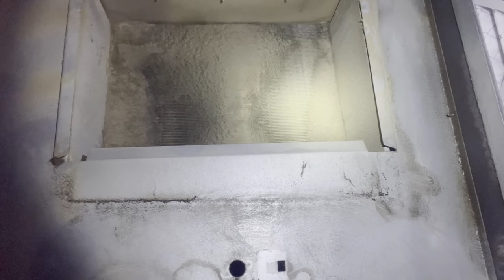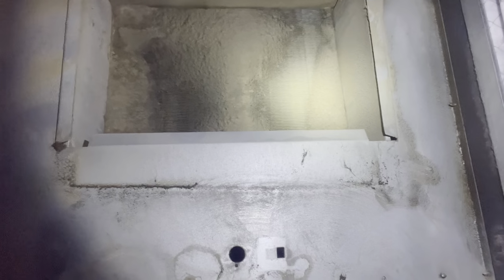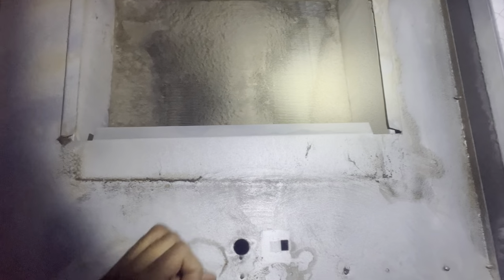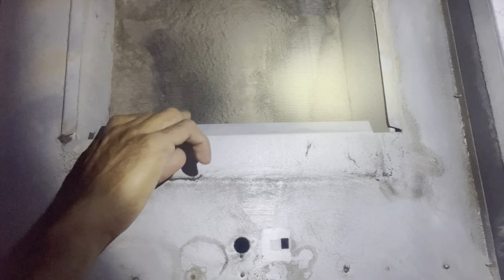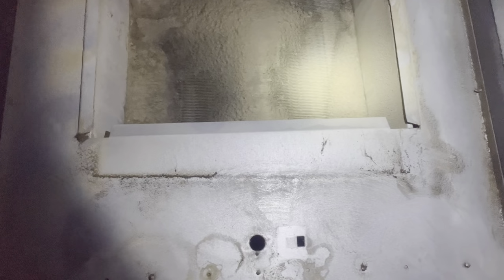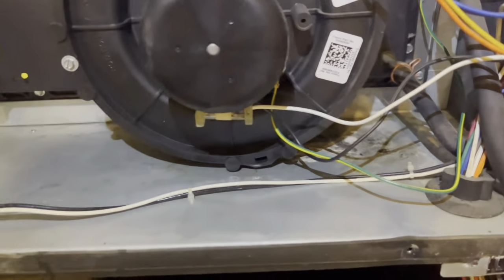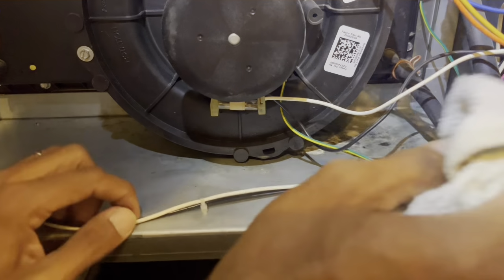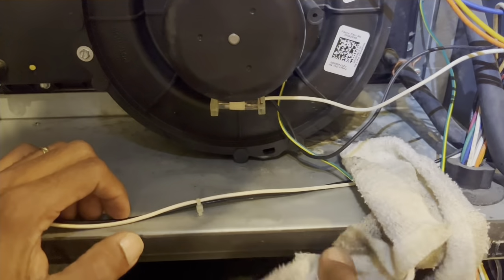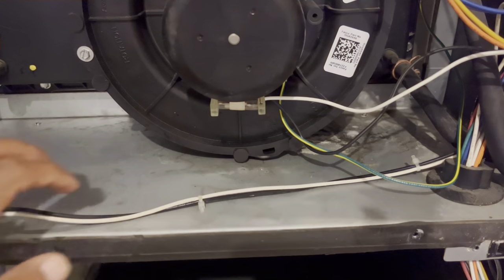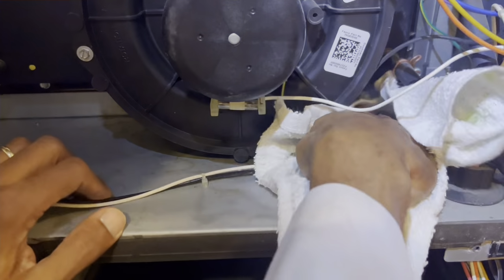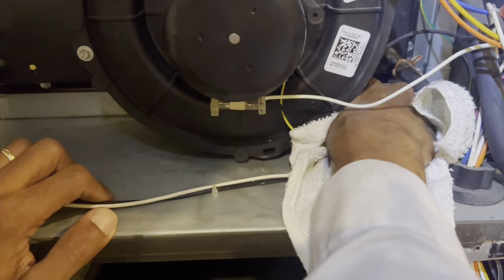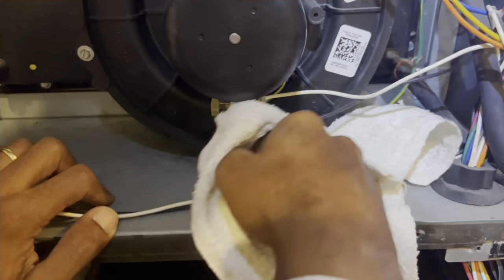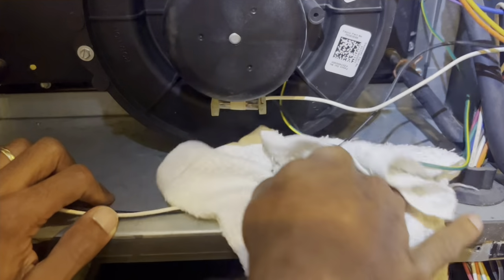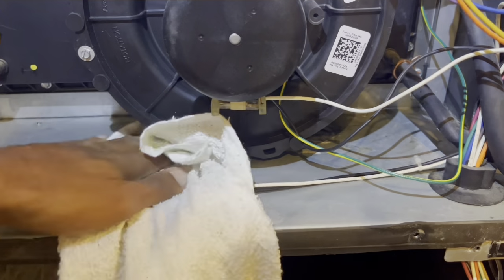Right here you can see that secondary heat exchanger on this high efficiency furnace. This may be a 95 to 96%, so of all the gas that is being put into it, this furnace may be losing 4 to 6, 7% of the energy put in. So we want to clean. That's why you want to have a good filter. You can see that secondary heat exchanger had a lot of dirt and debris in it. In a little bit, I'll take a brush, clean it out, and then I'll take the foam spray and clean it too.